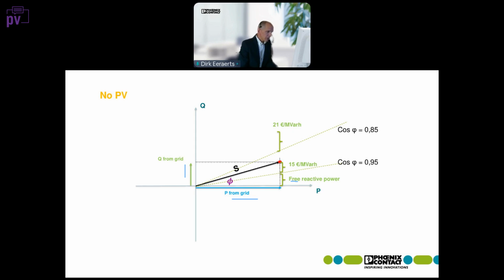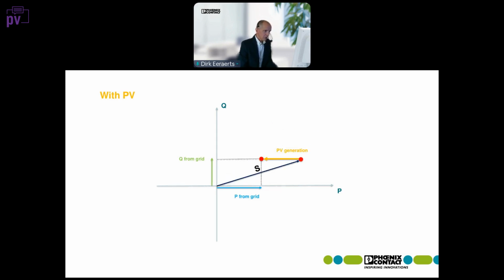This is without PV. Now, if we add PV to this side, what will happen is that the average operating point will move to the left because it's a generator. And if we don't control the inverters, it will be 100% active power. So it's a horizontal vector. So initially this customer will be quite happy because he gets less power from the grid, less active power, and the power from his own PV park should be lower in cost.